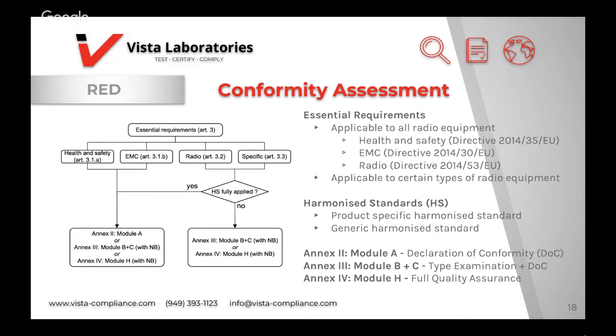Annex 3 is a type examination plus a declaration of conformity. So it's essentially a conformity to the type described in the EU type examination certificate, which is from the notified body review. And the manufacturer declares that it's their responsibility to conform to this type through their own internal production control. And lastly, full quality assurance. The NB in that case needs to perform an assessment to verify the compliance of the actual quality management system of the manufacturer with the relevant essential requirements of the directive.